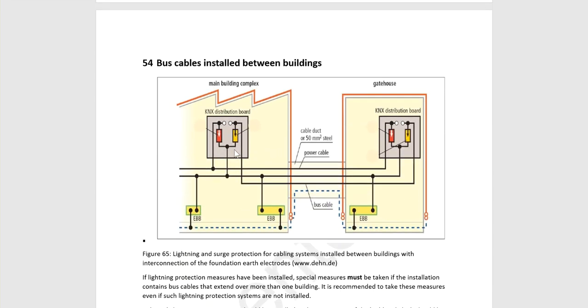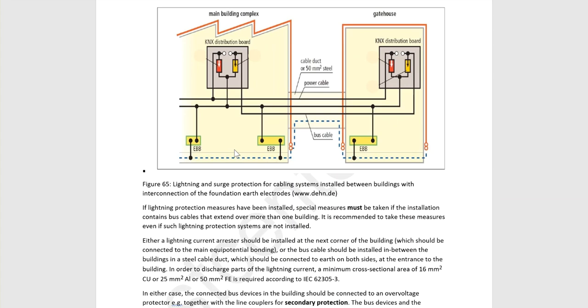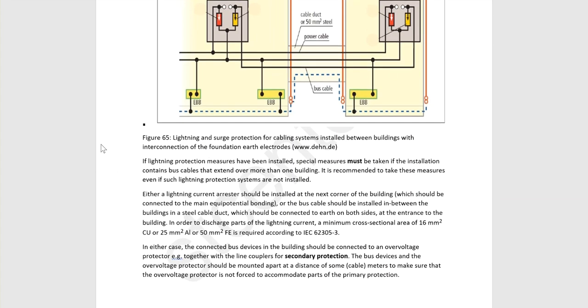So, bus cable installed between buildings. Between buildings also it is important. If lightning protection measures have been installed, a special measure must be taken if the installation contains bus cable that extends over more than one building. It is recommended to take these measures even if such lightning protection systems are not installed. Either a lightning current arrester should be installed at the entrance of the building, or the bus cable should be installed between the buildings in a steel cable duct, which should be connected to earth on both sides. So if you have this steel duct, you should connect it to the earth at the entrance to the building.